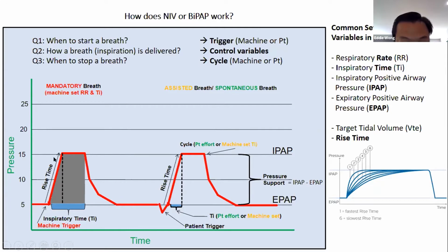You see the pressure waveform here, the pressure rise. How fast does the pressure rise from EPAP to achieve IPAP? How fast does the air enter your lung to open your lung? This setting is called rise time. Normally, the rise time setting you can set is either 1, 2, 3, 4, 5, or 6. But how fast depends on your comfort level, or in clinical terms, depends on your lung disease, obstructive or restrictive disease.